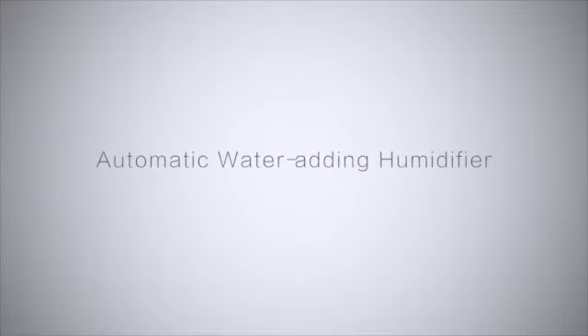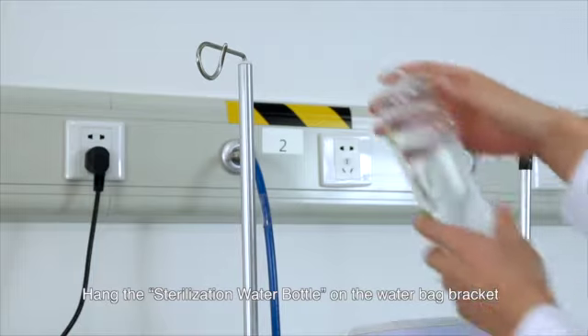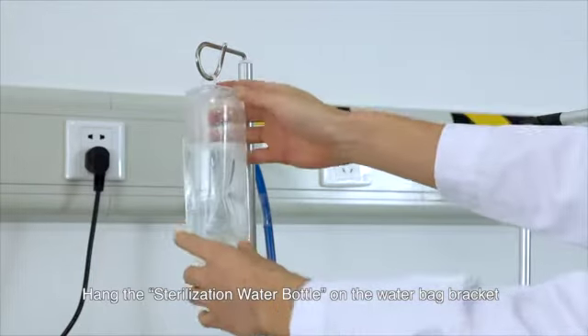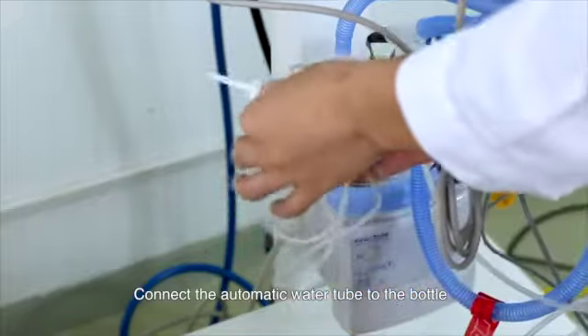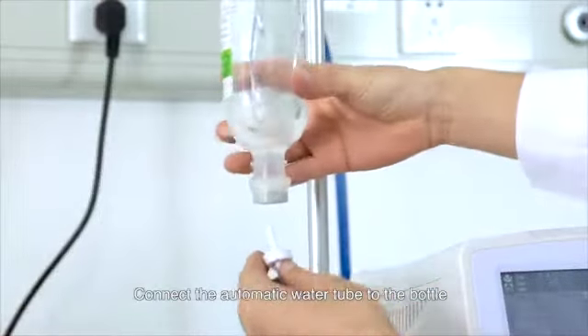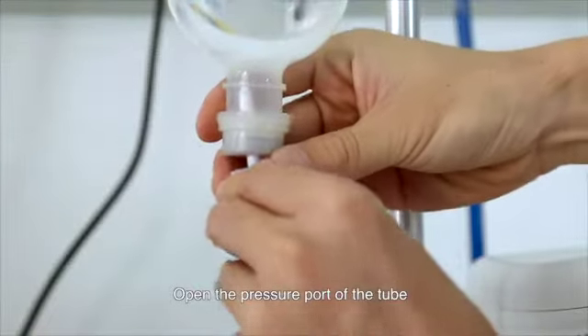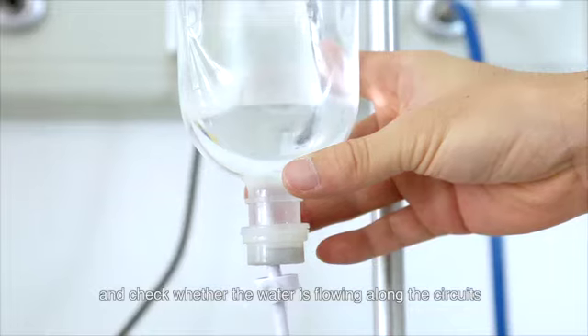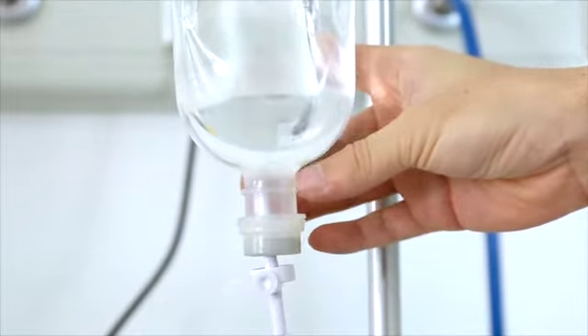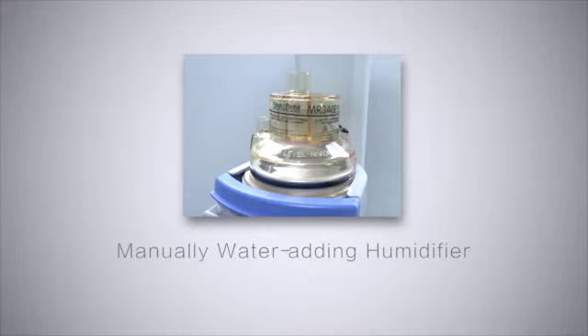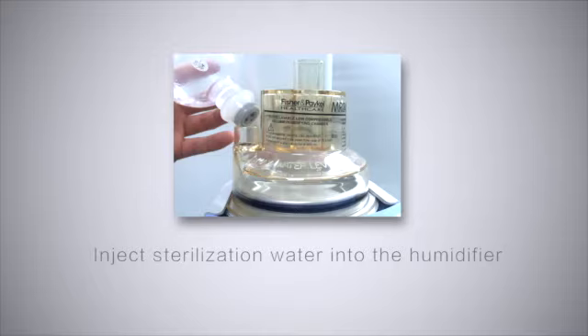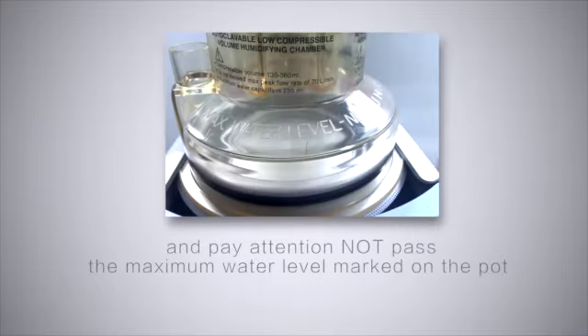There are two kinds of humidification pots. One is able to add water automatically and the other manually. Automatic water adding humidifier: hang the sterilization water bottle on the water bag bracket. Connect the automatic water tube to the bottle. Open the pressure port of the tube and check whether the water is flowing along the circuits. Manual water adding humidifier: inject sterilization water into the humidifier, and pay attention not to go past the maximum water level marked on the pot.